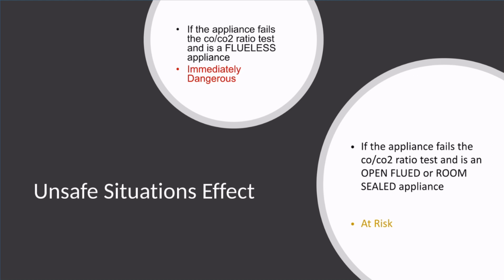And what effect does it all have on the unsafe situations? Well, if it's a flueless appliance and it fails the ratio test, it's regarded as immediately dangerous. Flueless, immediately dangerous. If it's an open flued or room sealed appliance and it fails the ratio test, then it's at risk. Flueless ID, open flued or room sealed, at risk.